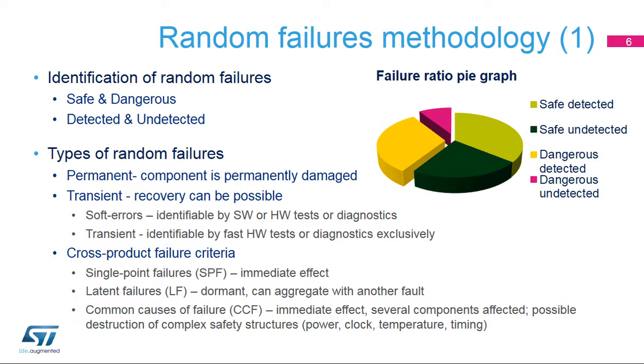For quantification purposes, safety standards recognize a safe failure fraction and diagnostic coverage. The safe failure fraction, or SFF, is the ratio of the rate of safe failures, including the rate of detected dangerous failures, to the total failure rate — safe failures as well as detected and undetected dangerous failures. The diagnostic coverage, or DC, is the ratio of the probability of detected dangerous failures to the probability of all the dangerous failures.